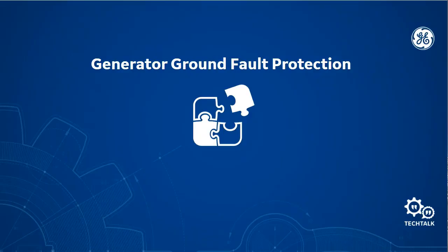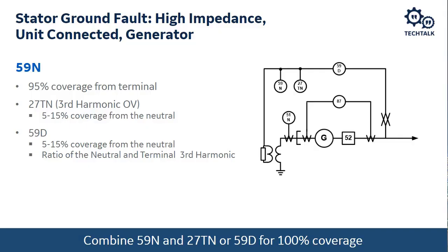We talked about the various grounding methods for generators, so let's talk about how we protect for those various grounding methods in the generator. First we're going to talk about high impedance grounded, which we mentioned is usually through a grounding transformer. We talked about previously that in high impedance or ungrounded systems, since there's no detectable ground fault current flowing, we have to use voltage. In this case, the overvoltage element. The overvoltage element is basically measuring the voltage on the neutral. That gets hooked up to our relay, or we can calculate it from the three-phase VTs, as we mentioned.